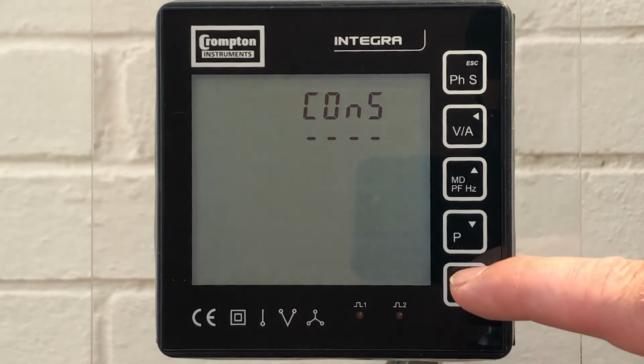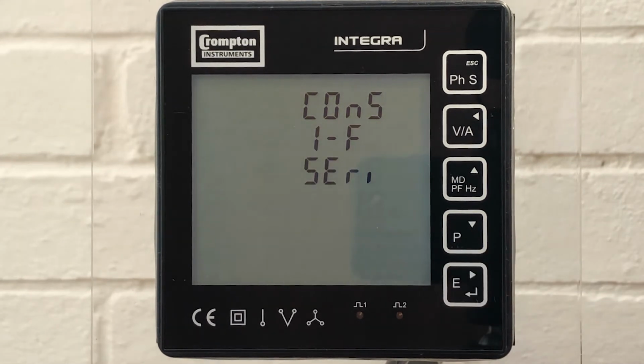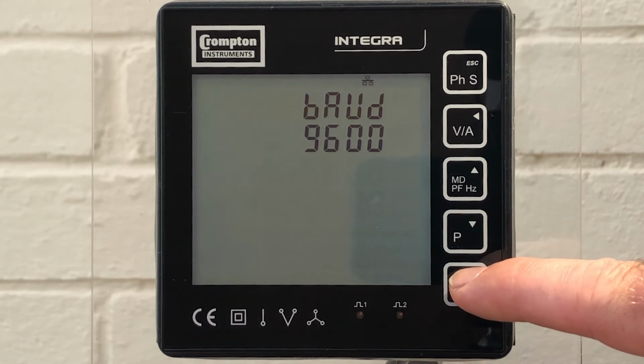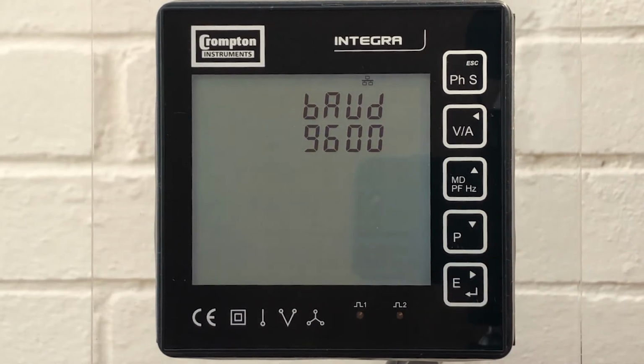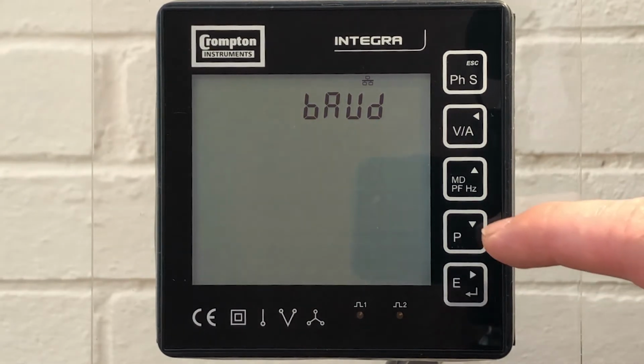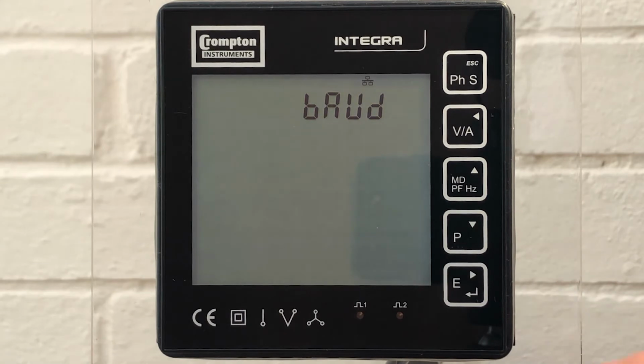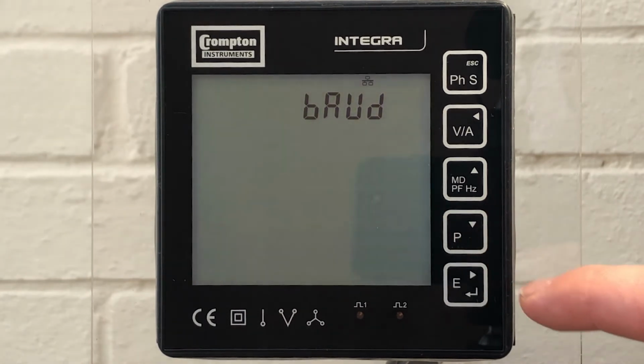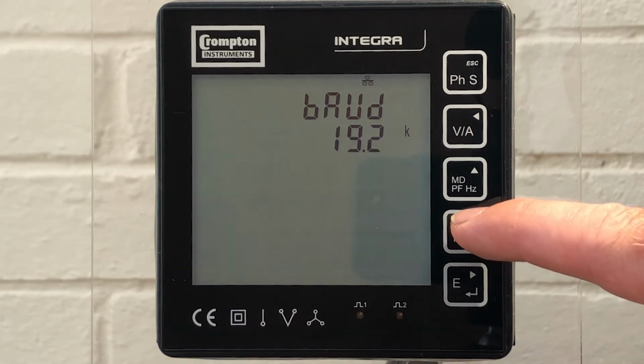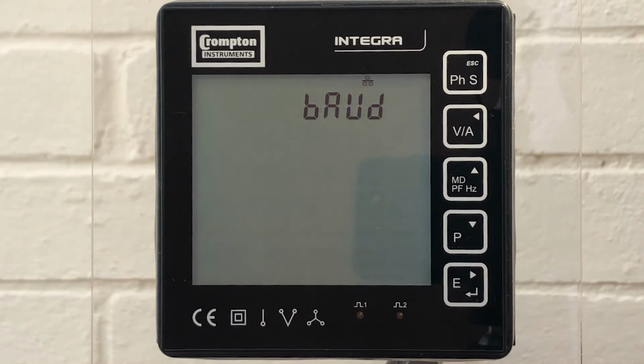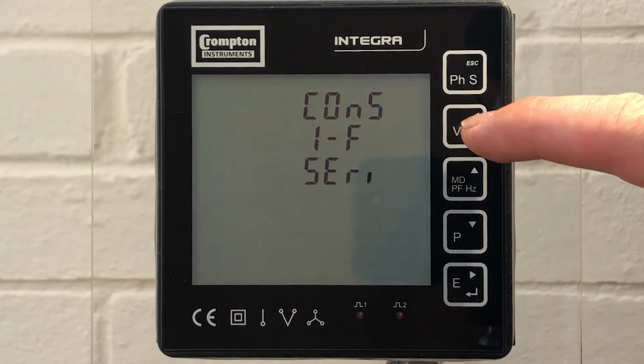The next settable feature is the communications. To go into the communications setting, press the E button, and the first setting we're presented with is the baud rate of our communications. The available options are 4800, 9600, 19200 or 38.4 kilobits per second. We'll set ours at 9600.